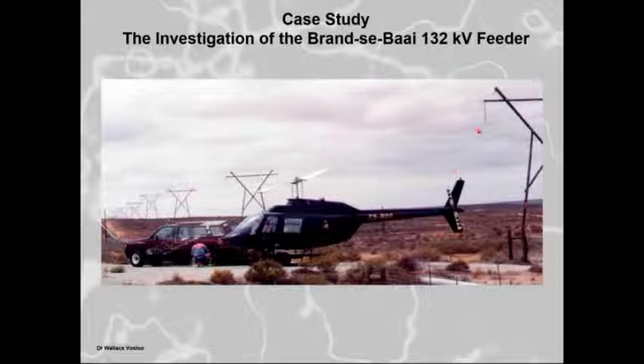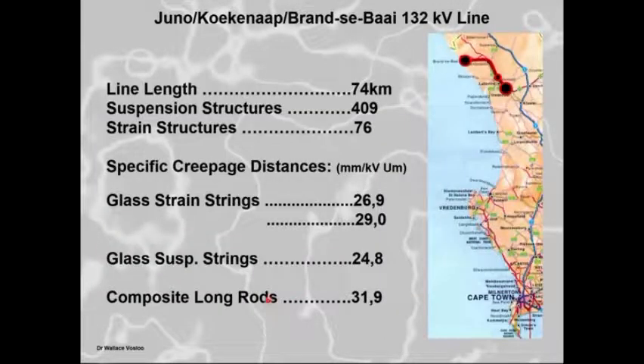Now, this is the line. You can see it's a wood pole structure, 132 kV running in, and it's in a desert marine environment. So it is a fairly highly polluted environment, but most of the line is running from the inland side. Let me show you. The line is about 74 kilometers, and it's running here inland from one of our big substations. It's running from there to a smaller substation, and then from that substation it's running down to the mining activity down here at Brandsebaai at the coast.